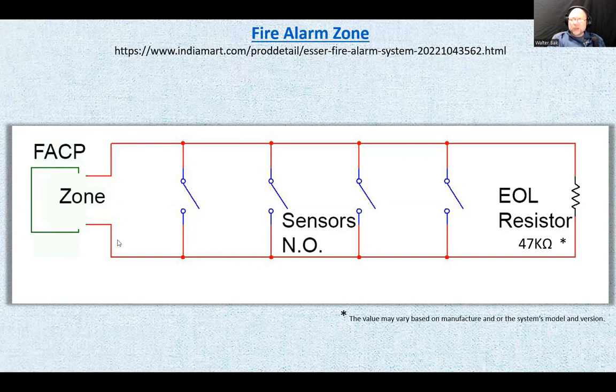You have the zone loop, and it is terminated with something that's called an end of line resistor. Quite often it's 47 kilo ohms, but this might vary depending on the model number and manufacturer of the alarm system. Now, that end of line resistor is what it says, nomen omen. The name defines the purpose. End of line. It should be at the end of the line. Is the system going to work if you take that resistor and place it right at the terminals at the panel? Yes, the system is going to work, but it's not going to work properly.